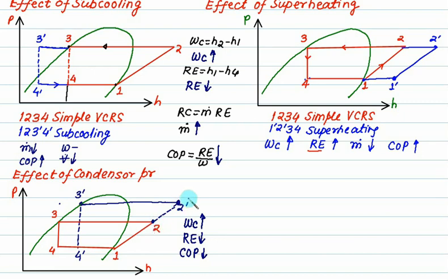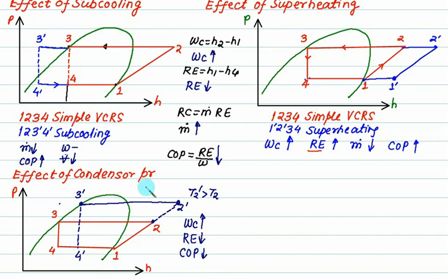From this analysis, if condenser pressure decreases, compressor work decreases, RE increases, and COP increases. This means the condenser pressure should be kept as low as possible — we should avoid high condenser pressure.